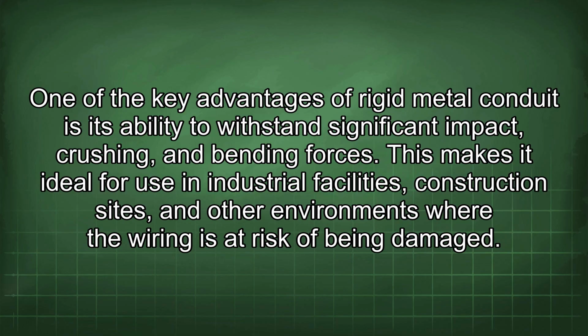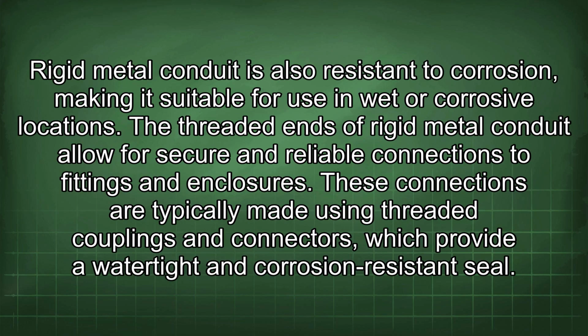One of the key advantages of rigid metal conduit is its ability to withstand significant impact, crushing, and bending forces. This makes it ideal for use in industrial facilities, construction sites, and other environments where the wiring is at risk of being damaged. Rigid metal conduit is also resistant to corrosion, making it suitable for use in wet or corrosive locations. The threaded ends of rigid metal conduit allow for secure and reliable connections to fittings and enclosures. These connections are typically made using threaded couplings and connectors, which provide a watertight and corrosion-resistant seal.